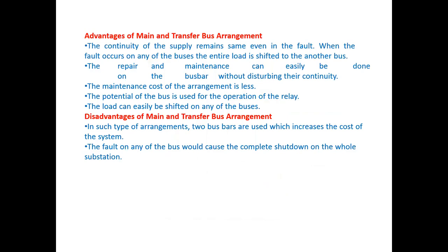The continuity of supply is maintained even during a fault — when a fault occurs on any one bus, the entire load is shifted to the other bus (transfer bus). Repair and maintenance can be done on the bus bar without disturbing continuity. The maintenance cost is low, and the load can easily be shifted to any other bus. Disadvantages: a fault on any bus causes a complete shutdown of the whole substation.